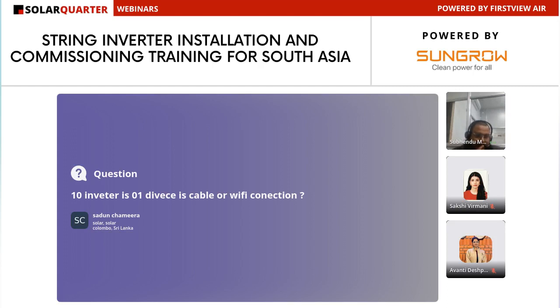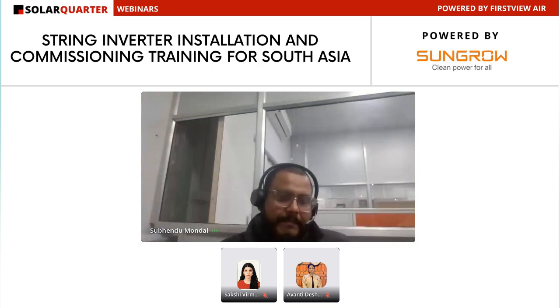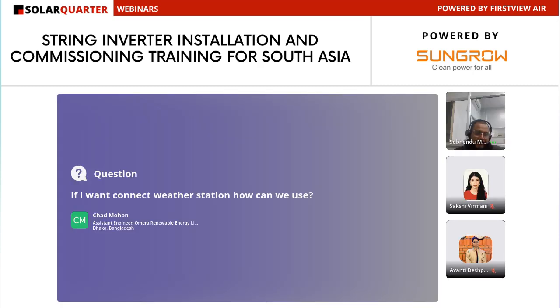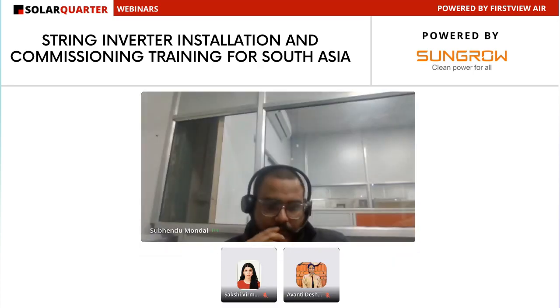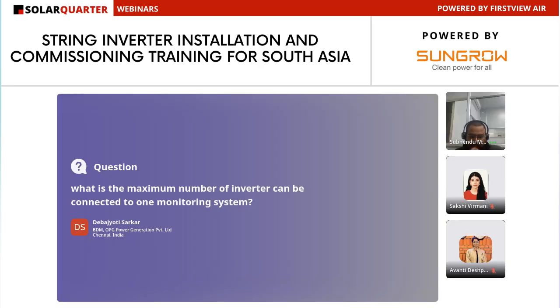10 inverters are one device, cable or Wi-Fi connection. If I want to connect a weather station, how do I use it? It's a third party device. You can use the communication board. For power line communication, you can connect a maximum of 40 devices in parallel.